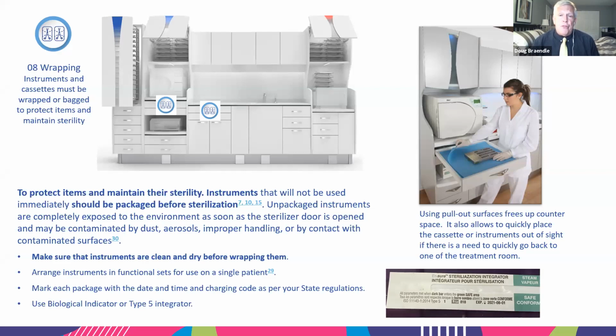And on that same Thursday, you're going to run your BI later on that day, but all of a sudden you run this and it fails. Here's what I would do. I would take another integrator, another type 5 integrator, put it in another pouch, seal it. Don't move any of those instruments that are on the inside. Run it again. If by chance you have 2 failures in a row, I'm fairly confident that even if your machine's not giving you any error codes, you have an issue.